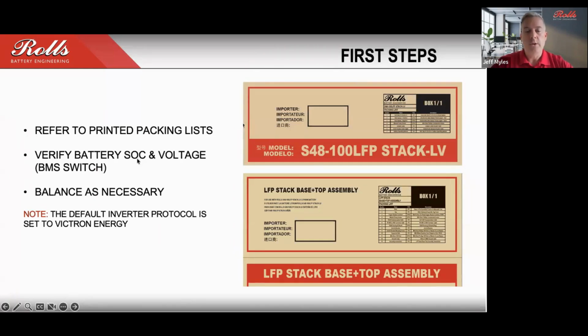So when you receive those units, you're going to have those two SKUs. One is obviously the battery, and the other SKU is the base and top assembly. On the cartons, we've also included the packing list for each of those components, and that includes everything from the bus bar connections, the ground connections, and so on. We've itemized all of that in a packing list directly on the carton. The reason is so that you can verify that all of the components are included in the box, but also ensure that you have the current copy of the manual and so on.